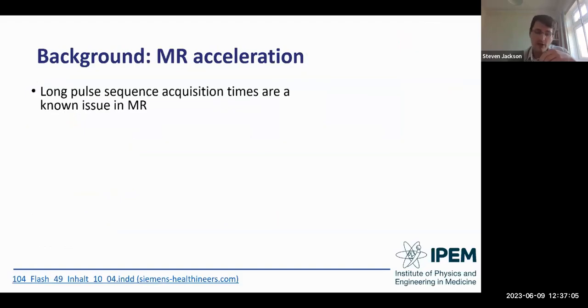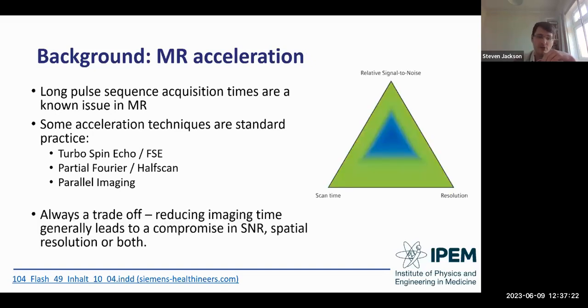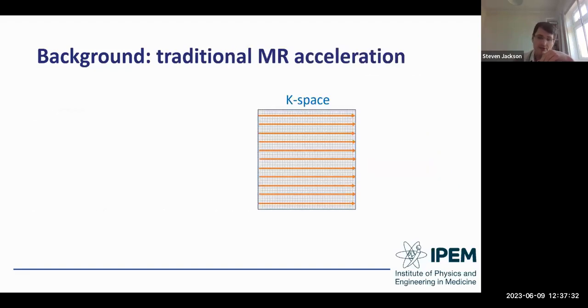We'll do a bit of background physics on MR acceleration. Long pulse sequence acquisition times are a known issue in MR. Some acceleration techniques are standard practice and have been around for many years — for example turbo spin echo, partial Fourier or half scan, and parallel imaging. But historically there's always been a trade-off: reducing imaging time generally leads to compromising SNR, spatial resolution, or both, certainly for routine imaging.